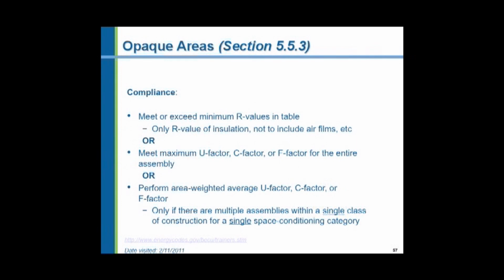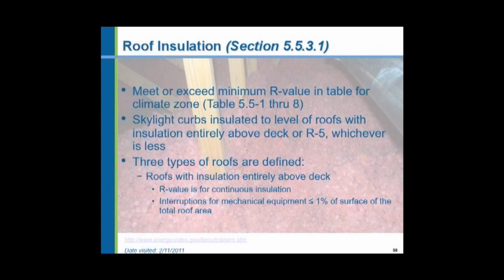However, we can use the overall U value heat transfer. In order to do that, we go to Appendix A. And in Appendix A, there are myriad different variations of wall construction and ceiling and roof construction. And they have calculated the U values. They've put different insulation in, different sidings, different sheathings, and they have calculated the U values. If you're going to use the U value, the U times area alternative, rather than just listing the insulation itself, then you're going to go to Appendix A and pull those values. Again, the roof insulation must meet the values that are shown in those tables.